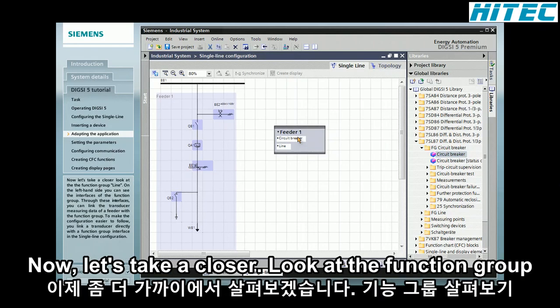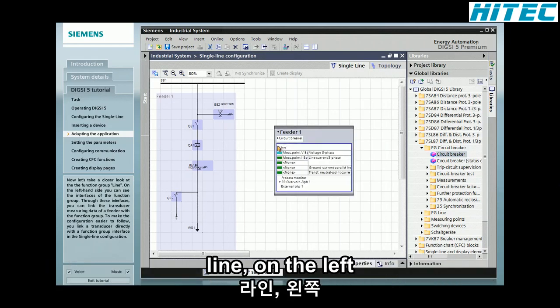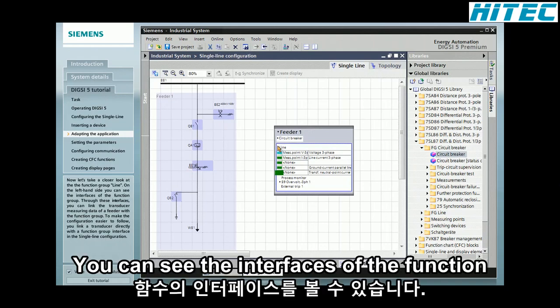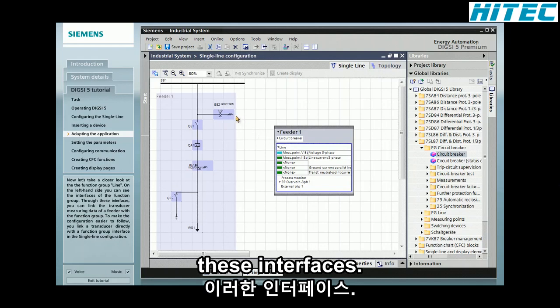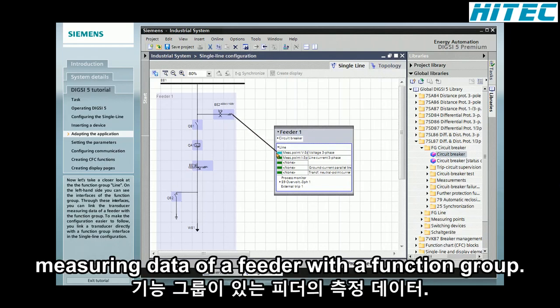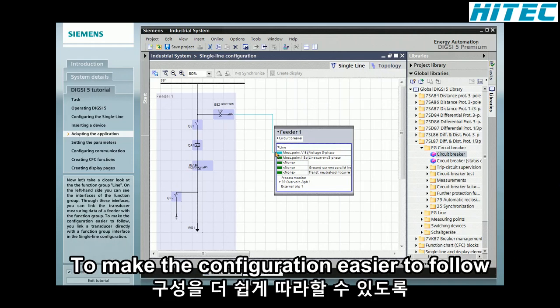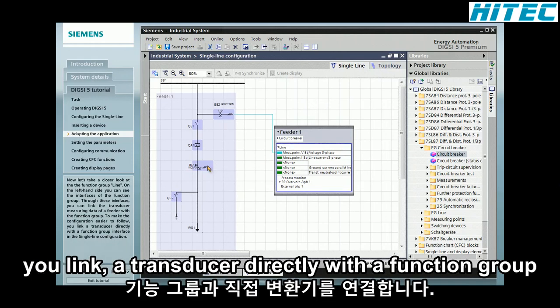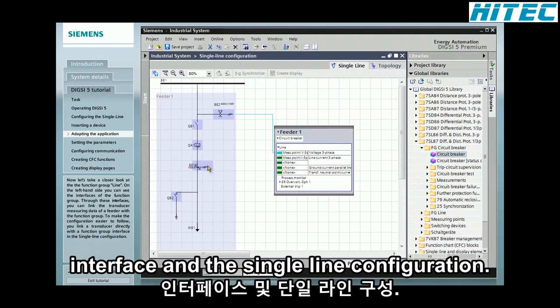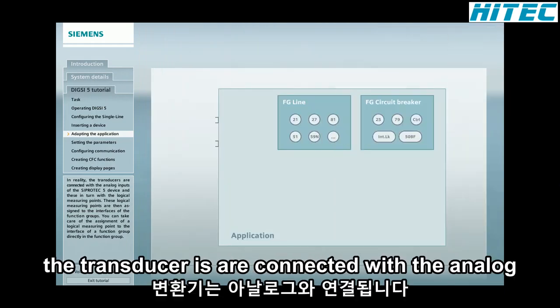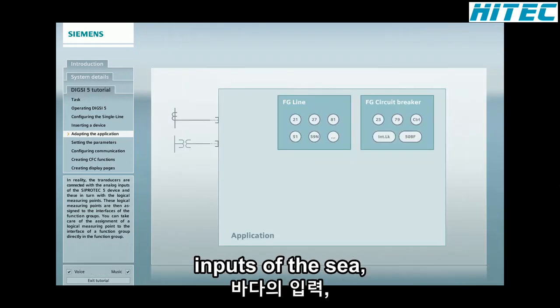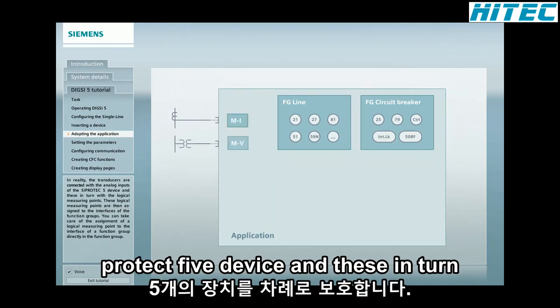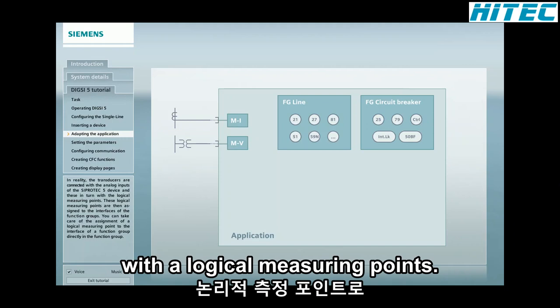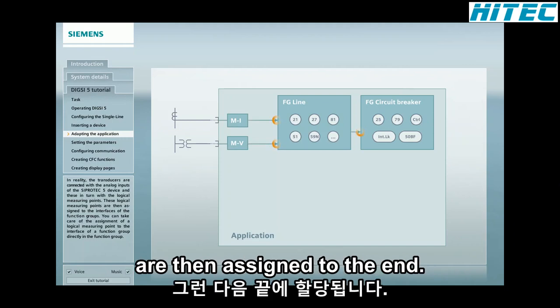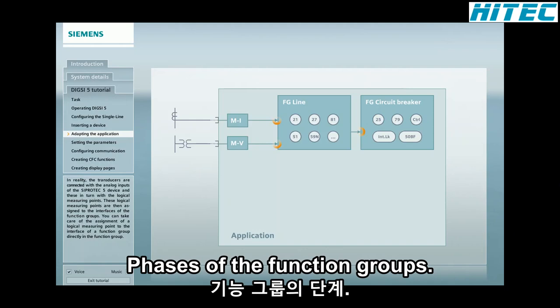Now let's take a closer look at the function group line. On the left-hand side, you can see the interfaces of the function group. Through these interfaces, you can link the transducer measuring data of a feeder with a function group. To make the configuration easier to follow, you link a transducer directly with the function group interface in the single-line configuration. In reality, the transducers are connected with the analog inputs of the SIPROTEC 5 device, and these in turn with the logical measuring points. These logical measuring points are then assigned to the interfaces of the function groups.